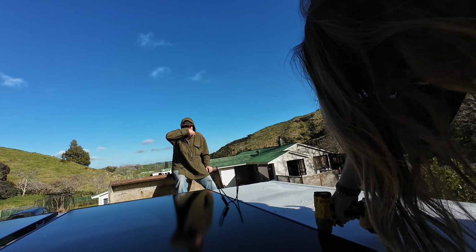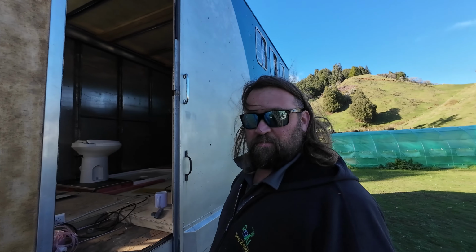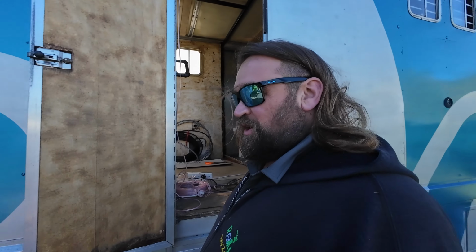You just gotta hook up the end panels. Yeah, you gotta run the extra leads down to the middle to the inverter and put the fuse in. So one on each end of the line of panels. We can't hook them up until we put the fuse in, because as soon as you plug it into the panels, the lines become live.